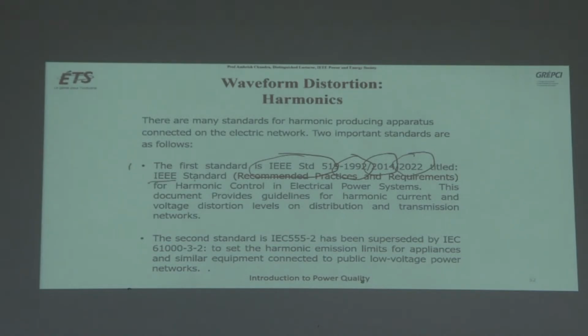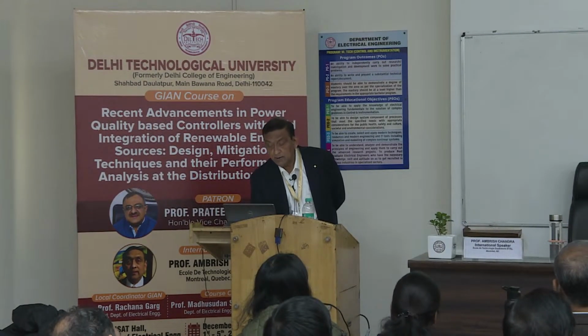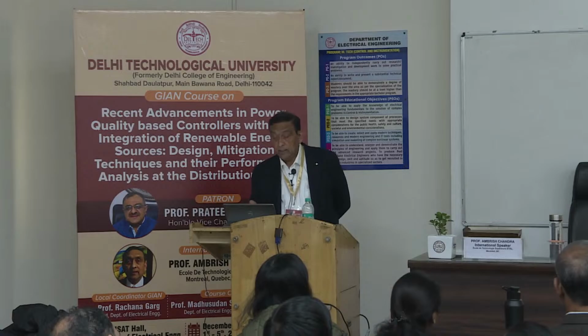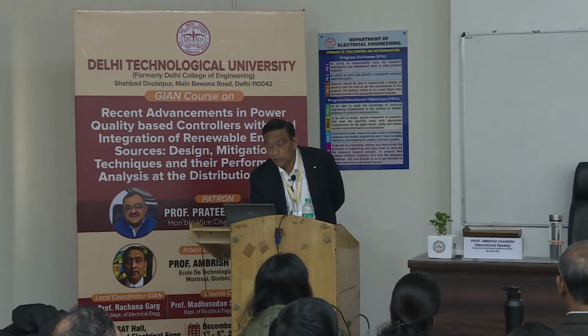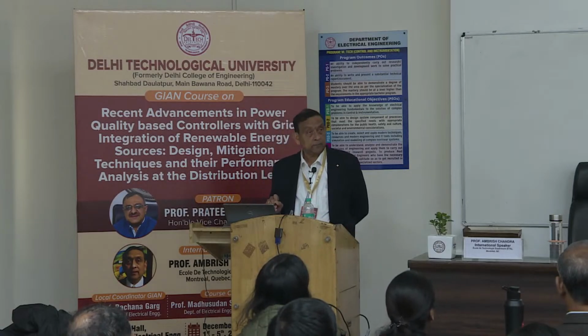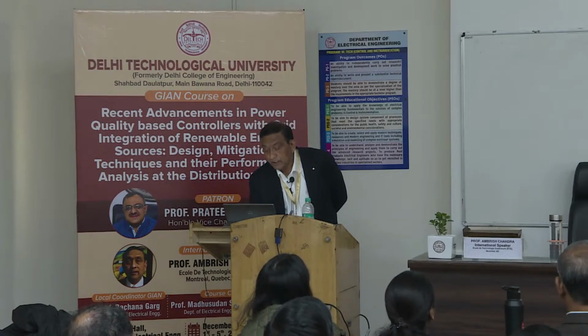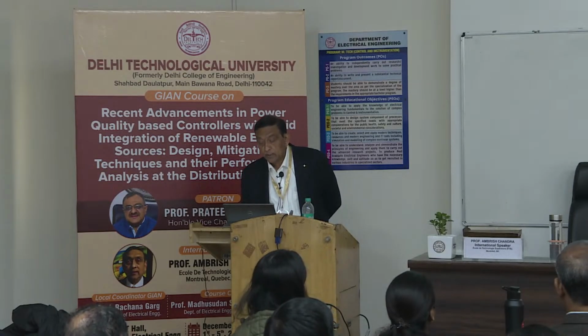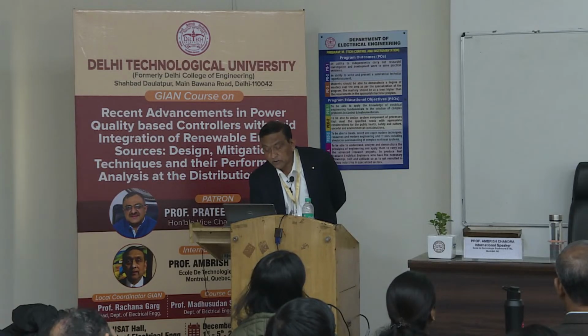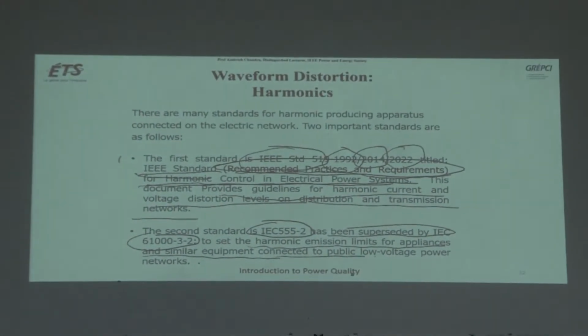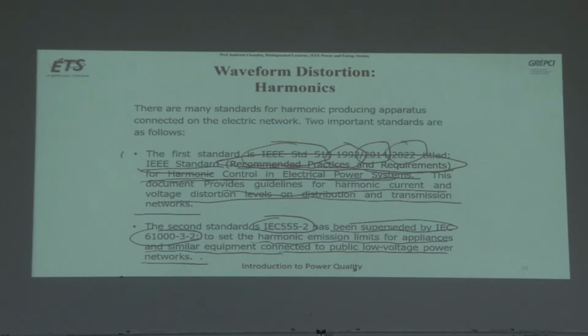So what is the title? Initially it was IEEE standard recommended practices and requirements for harmonic control in electric power systems. But later, in the modification, they dropped this term, so now it is IEEE standard for harmonic control in electric power systems. This document provides guidelines for harmonic current and voltage distortion levels on distribution and transmission networks. And there was a second standard, IEC 555-2, but it has been superseded by 61000. This sets the harmonic emission limits for appliances and similar equipment connected to the public low voltage power network. Especially European countries follow it, but in North America we follow IEEE standards.